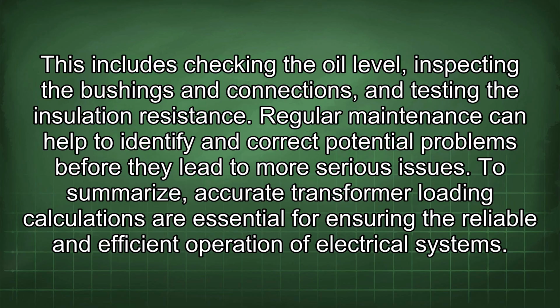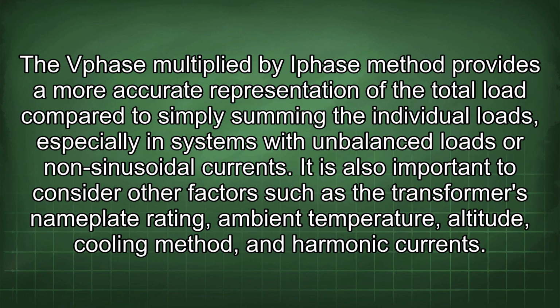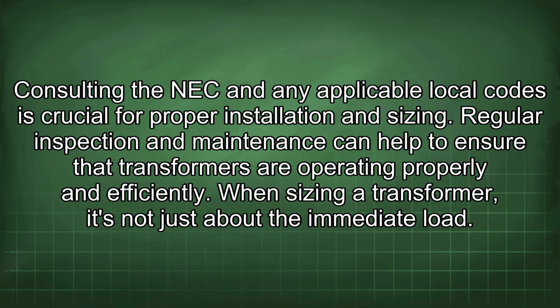To summarize, accurate transformer loading calculations are essential for ensuring the reliable and efficient operation of electrical systems. The Vphase multiplied by Iphase method provides a more accurate representation of the total load compared to simply summing the individual loads, especially in systems with unbalanced loads or non-sinusoidal currents. It is also important to consider other factors such as the transformer's nameplate rating, ambient temperature, altitude, cooling method, and harmonic currents. Consulting the NEC and any applicable local codes is crucial for proper installation and sizing. Regular inspection and maintenance can help to ensure the transformers are operating properly and efficiently.